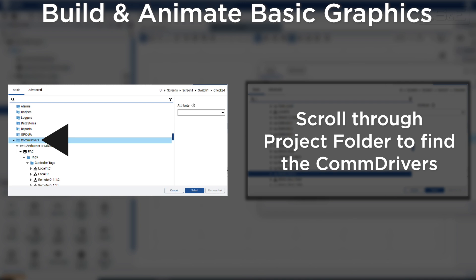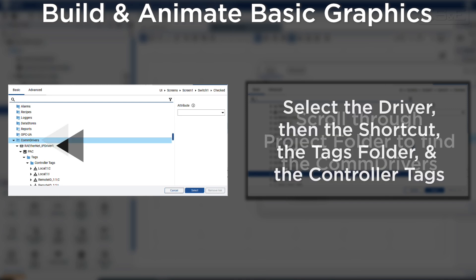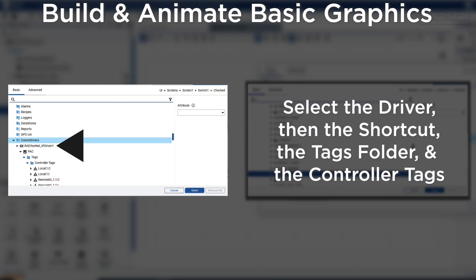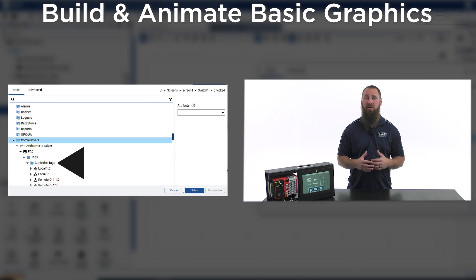If you don't remember the tag name, then we need to scroll down under the project name folder to find the com drivers folder, open it and go to the driver, then the shortcut, then the tag folder, and finally the controller tag folder. This folder structure was created for us during the tag import wizard.